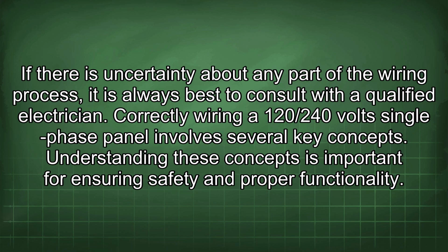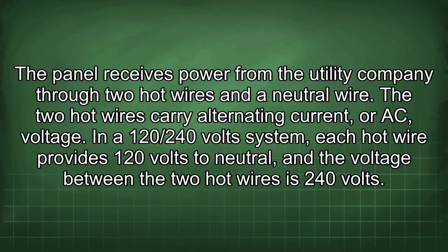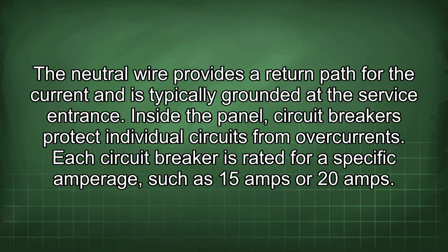Correctly wiring a 120/240 volt single-phase panel involves several key concepts. Understanding these concepts is important for ensuring safety and proper functionality. The panel receives power from the utility company through two hot wires and a neutral wire. The two hot wires carry alternating current or AC voltage. In a 120/240 volt system, each hot wire provides 120 volts to neutral, and the voltage between the two hot wires is 240 volts. The neutral wire provides a return path for the current and is typically grounded at the service entrance.